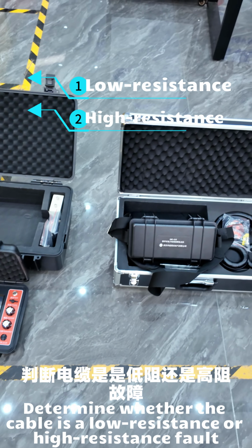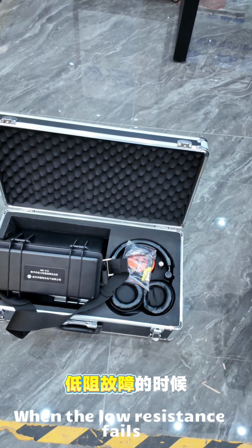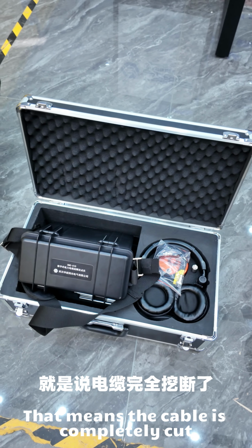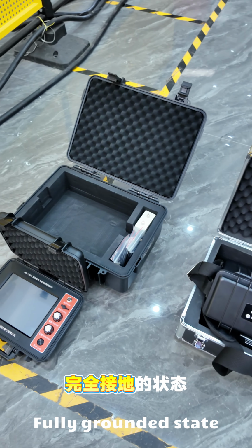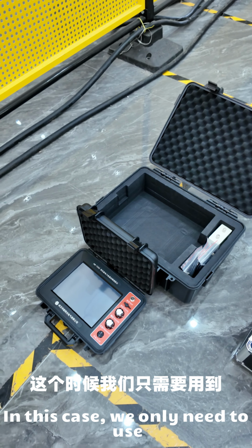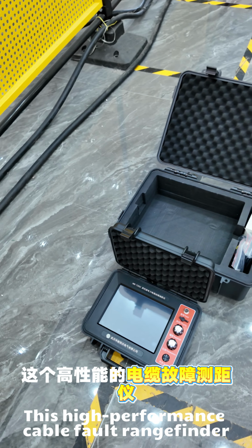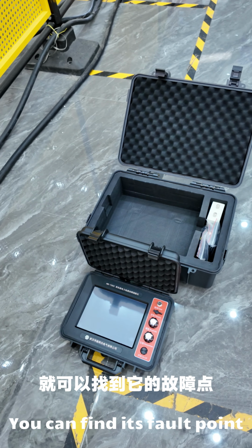to determine whether the cable is a low resistance or high resistance fault. When the low resistance fails, that means the cable is completely cut, in a fully grounded state. In this case, we only need to use this high-performance cable fault rangefinder. You can find its fault point.